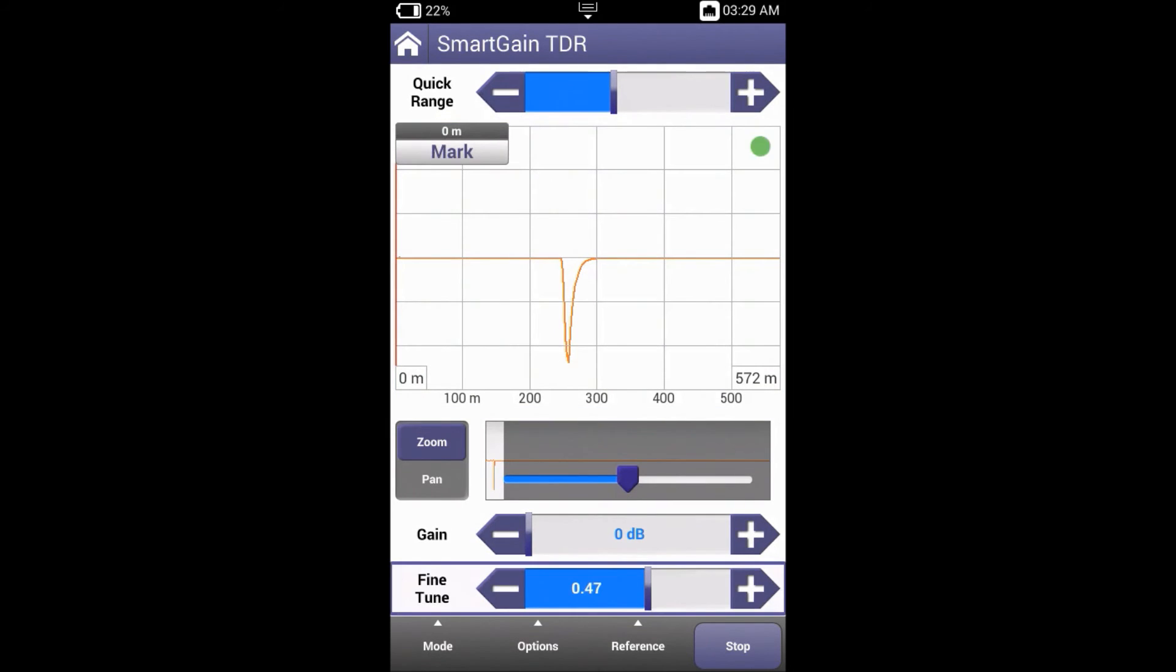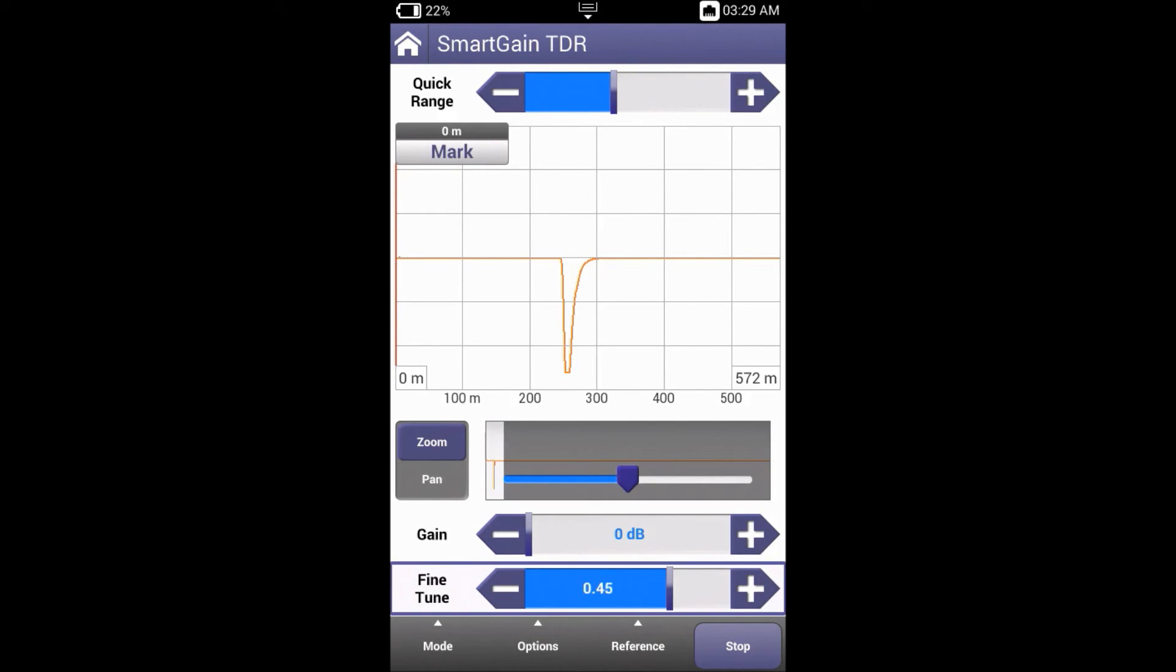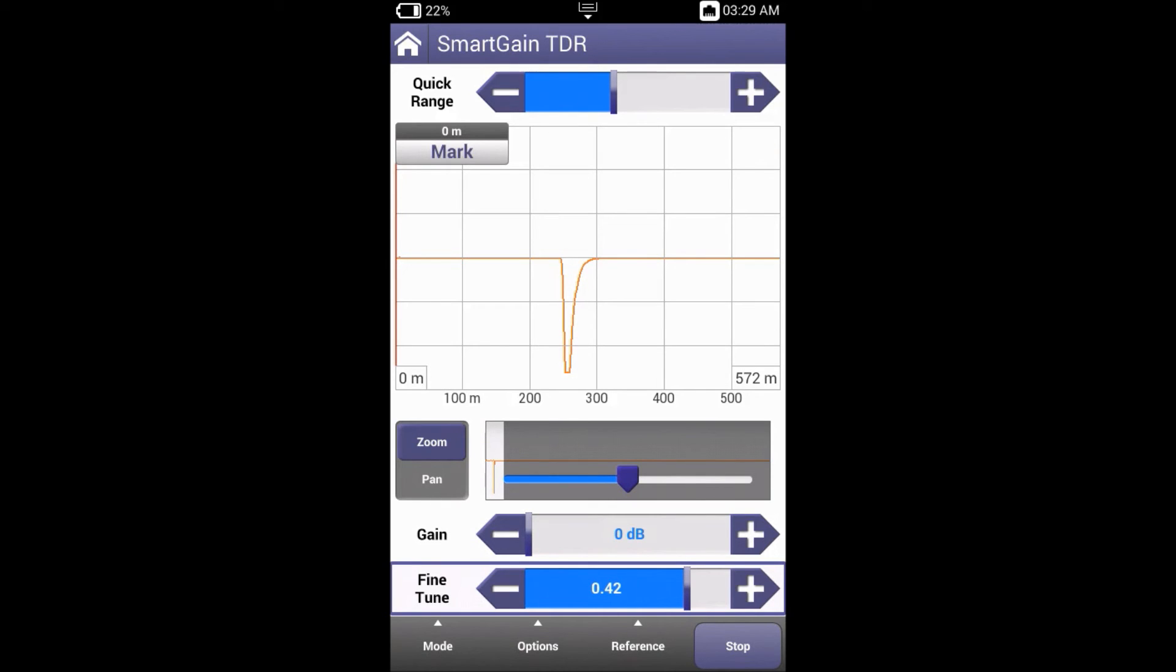The fine-tune function at the bottom of the screen enables you to select the dominant cable gauge. Plus and minus increases or decreases the fine tuning. You can increase and decrease about half a gauge. If you want to override smart gain settings, simply use control gain as in the standard TDR mode.